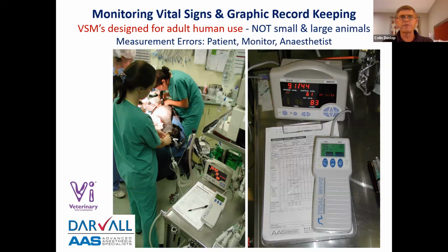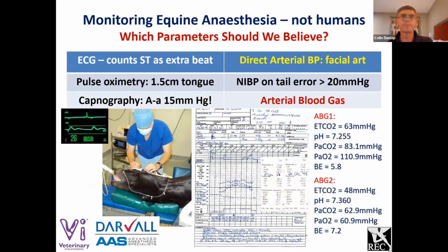The important message of this picture is, firstly, we're keeping an anaesthetic record. We still need to keep this information in a representative way that we can use in an instant in time. The second thing is that this equipment is all designed for human use, although in later times that blood pressure pulse oximeter monitor that you can see there was adapted with some changes for veterinary applications. But there are errors associated with using this equipment, some from the patient, some from the equipment, and some from the people using it. And we'll try to address some of those things tonight.